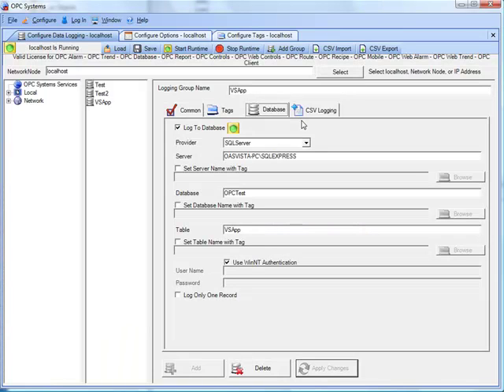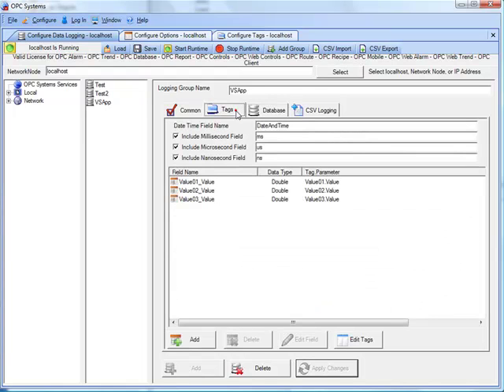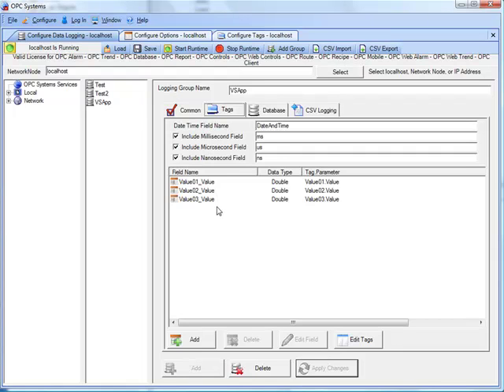To log data from a remote OPC system service, that's quite easy. Under the tags definition, you simply include the network node name, IP address, or domain name, in each of the tags that you want to retrieve data from. So when we're defining a new tag, instead of selecting a local service, we would enter in a remote service.